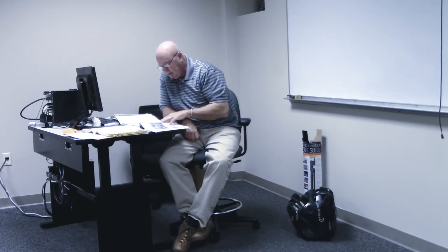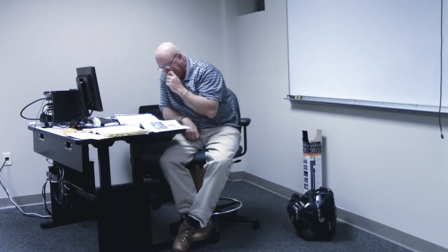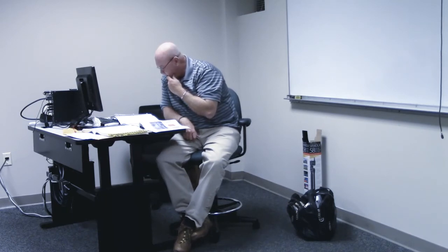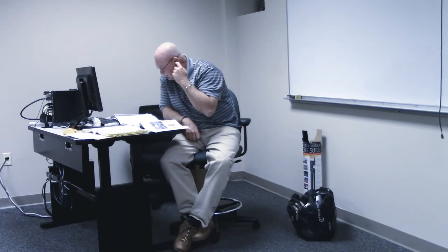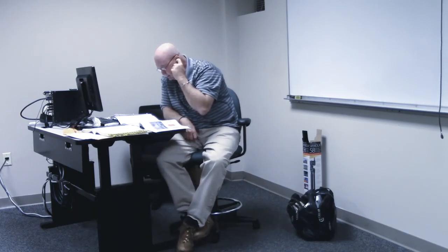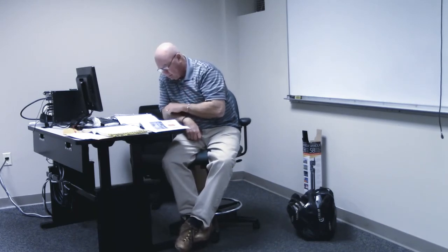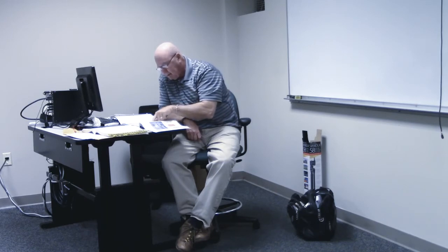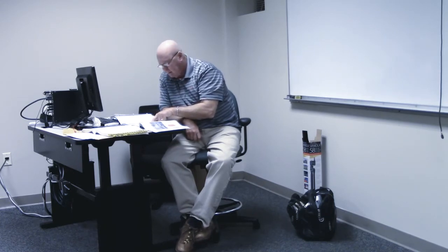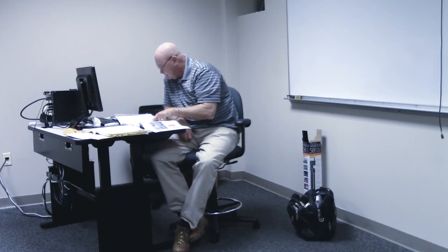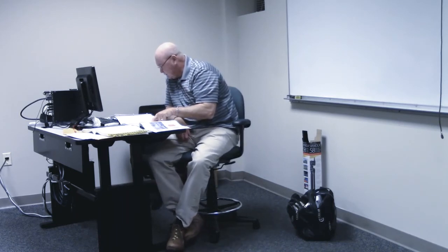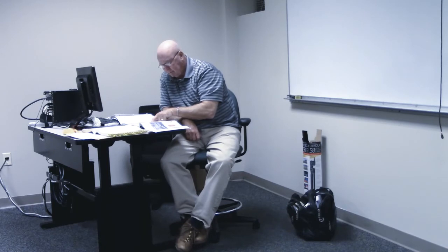On page 13, in a patient bed non-critical space, which is listed there on page 13 about right below those three bullet points: in addition to two branch circuits, each patient bed location must have a minimum of 8 receptacles. That's in a non-critical space. You've got to have 8 receptacles.